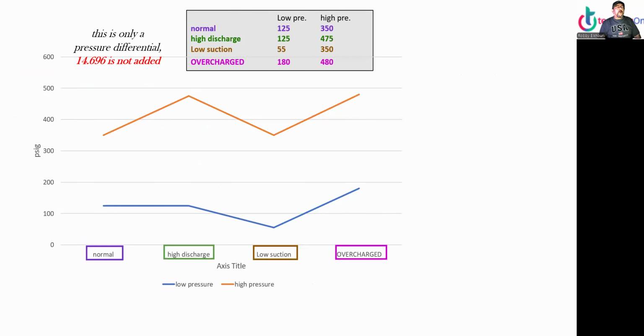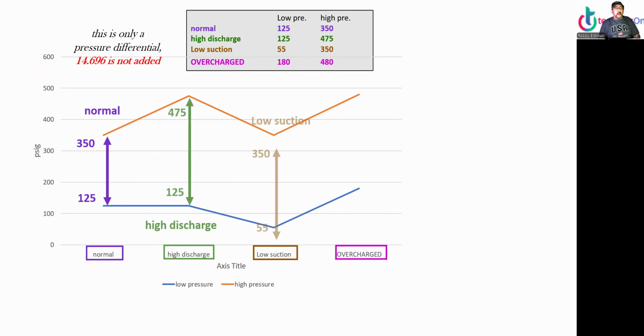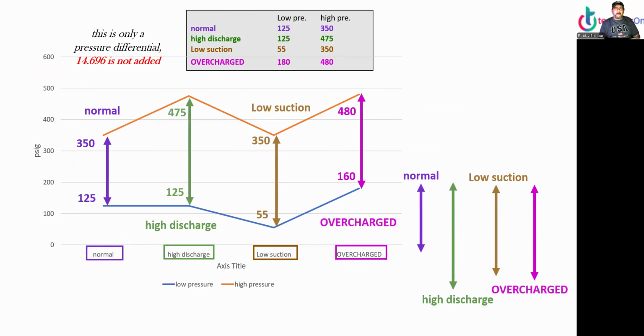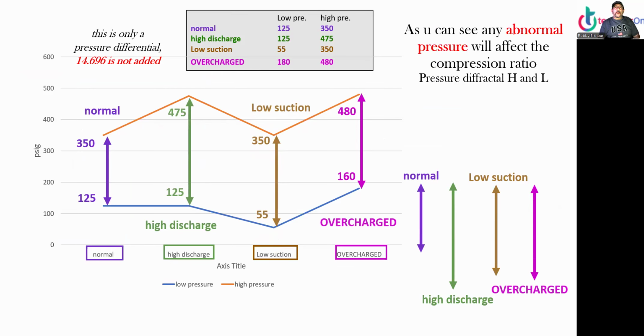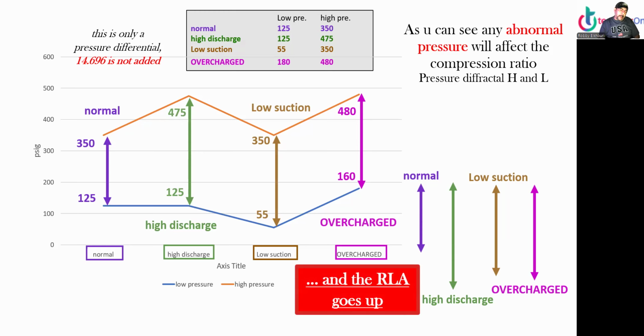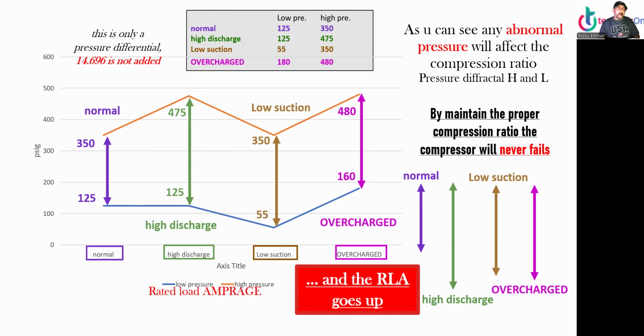All right, now, this is only a pressure differential. I did not add the 14.696. This is not compression ratio. This is just the pressure differential. So this is your normal pressure. If we have high discharge pressure, look at that arrow, bigger. We have low suction pressure, and overcharged. Any way you look at it, the pressure differential is going to be different. As you can see, abnormal pressure will affect compression ratio and pressure differential, high and low. And there goes the RLA. RLA is rated load amps, and I'll cover that later.